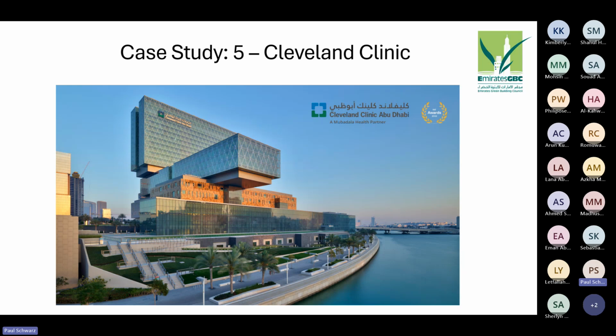So the design needed to account for ventilation of these extremely large generators and ensure surrounding communities weren't adversely affected. In this instance, the ventilation faced directly toward the Hilton Hotel across the creek. There were some interesting design procedures, but we managed to attenuate the 24 diesel generators so they could operate without affecting the nearby residential community.